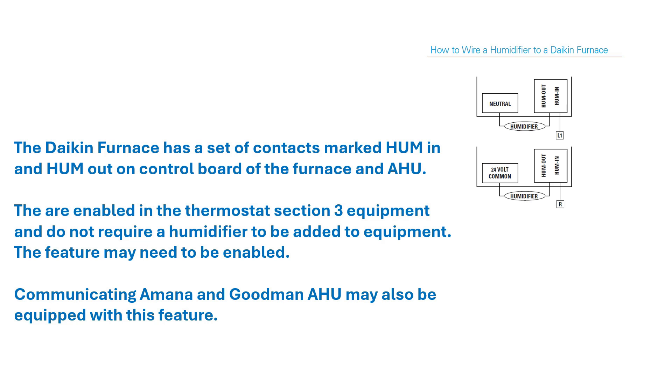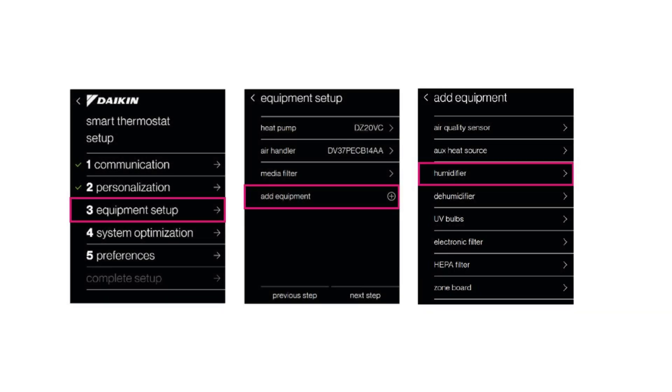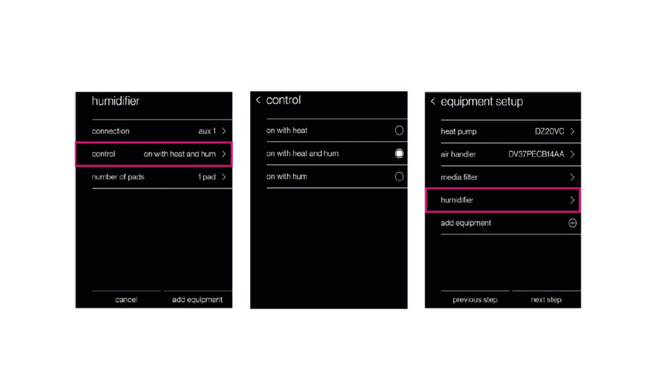You'll have to turn the humidifier contacts to the on position, which is done in the equipment setup under the furnace or air handler itself. But when adding a humidifier, we'll go to equipment setup, add equipment, and choose the humidifier. We'll then choose how we're going to control it — on with heat, on with heat and humidity, or just on with the humidity call.